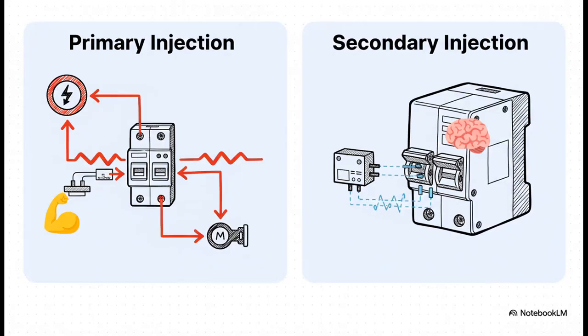When it comes to testing that trip unit, there are two main ways to go. Primary injection is the full system workout. Testers pump actual high-power current right through the breaker to make sure the entire chain of events works just like it's supposed to. Secondary injection, on the other hand, is more like a targeted brain scan. It connects right to the electronic trip unit to test its logic and response without having to send those massive currents through the whole circuit.